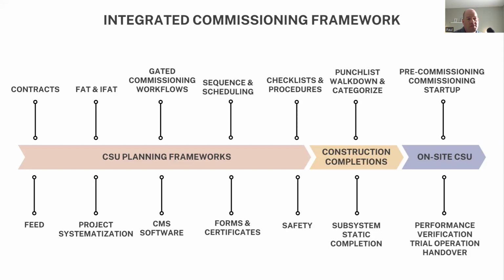Of course, our checklists and procedures need to be prepared in advance. There's no time during on-site commissioning to be thinking about or planning these activities, because it's too fast-paced. So we need to have all our checklists prepared in advance, all our commissioning procedures to verify our process control narratives, everything ready to go before on-site commissioning starts, so we can strictly focus on execution. All of these checklists, procedures, and inspection test records are loaded into our commissioning management software and tracked for completion so that nothing gets missed.